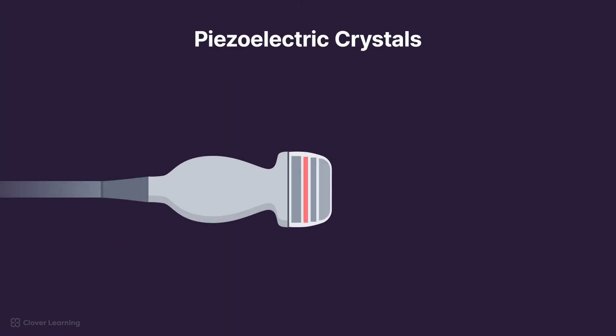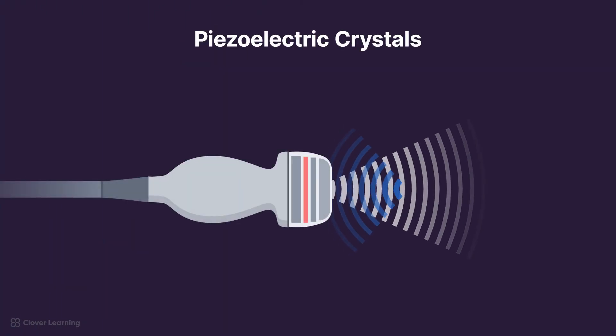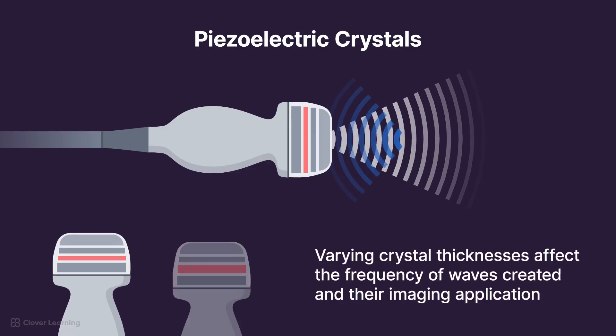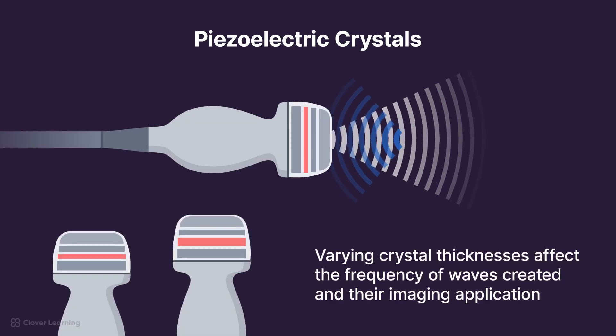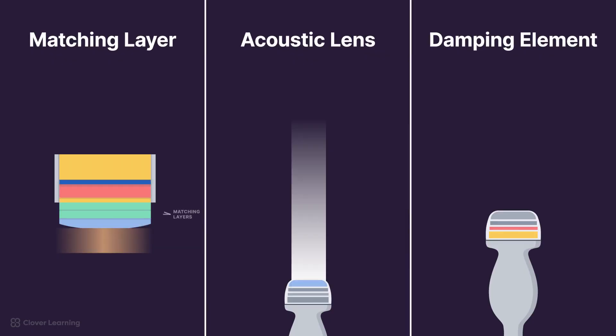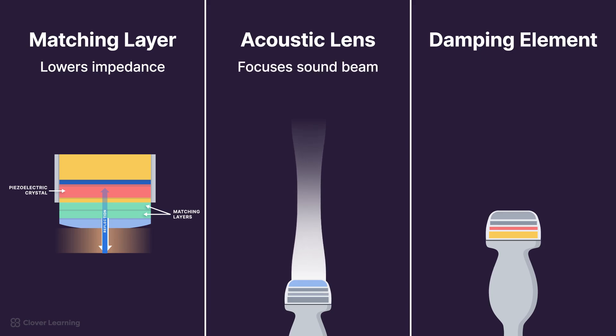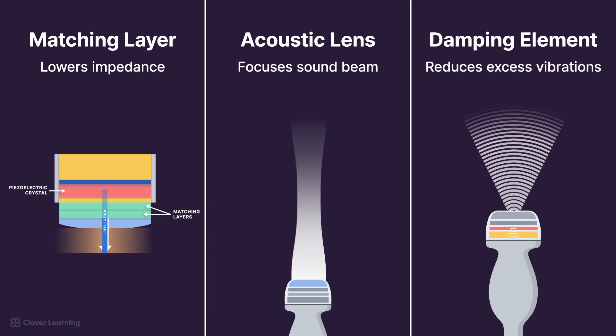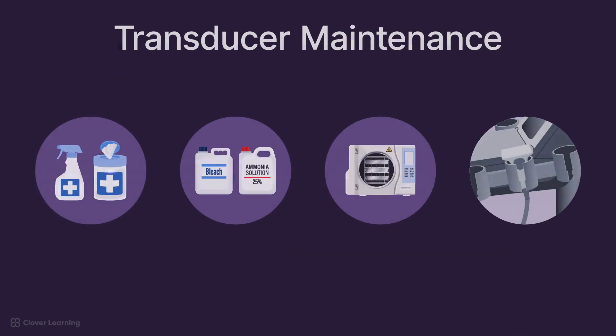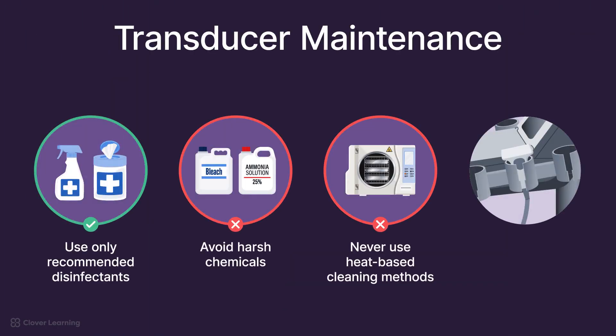The piezoelectric crystal generates and receives sound waves and comes in varying thicknesses which affects the frequency of waves created and their imaging application. The matching layer lowers impedance between the crystal and the patient's tissue. The acoustic lens focuses the sound beam and the damping element sharpens image clarity by reducing excess vibrations. Proper cleaning, storage, and damage prevention are essential for ensuring reliable imaging and patient safety.